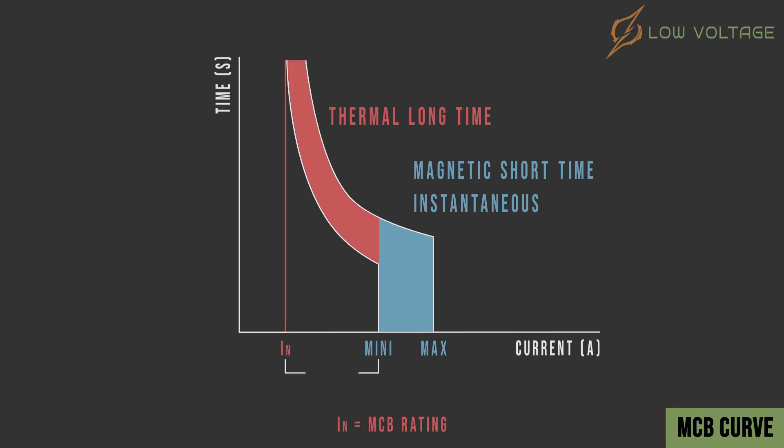Now we can say if the current is between IN and minimum magnetic settings, the MCB will trip thermally in delayed time. And if the current is between the minimum and maximum magnetic settings, the MCB will trip magnetically in short instantaneous time.